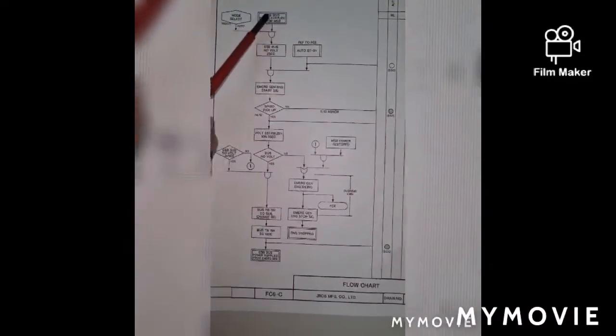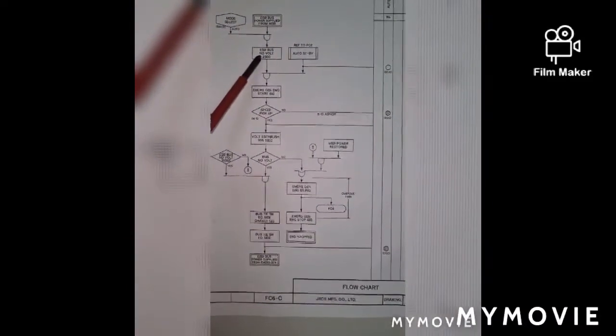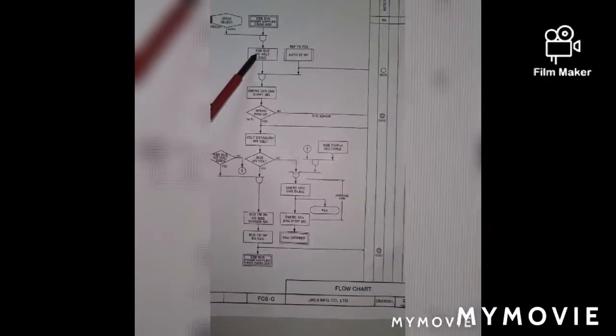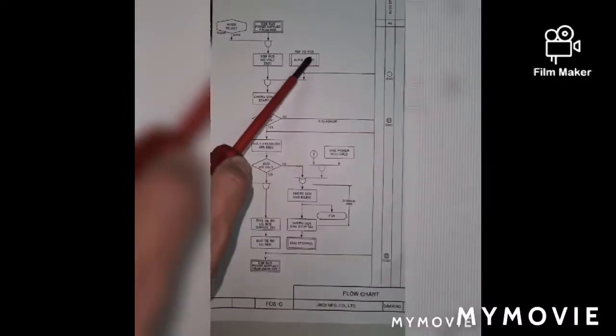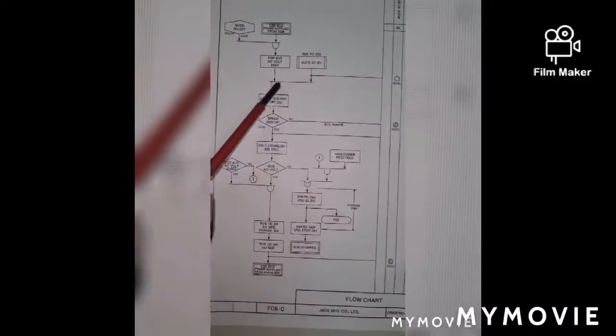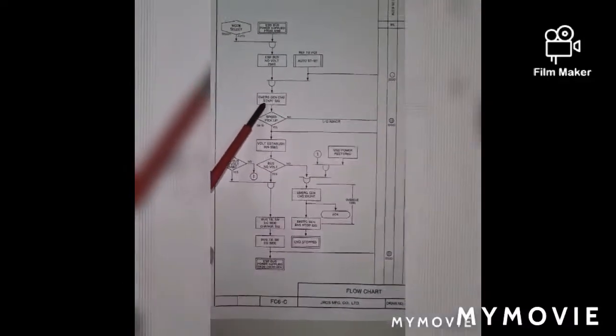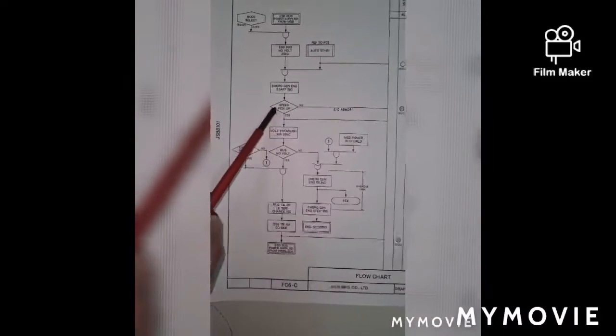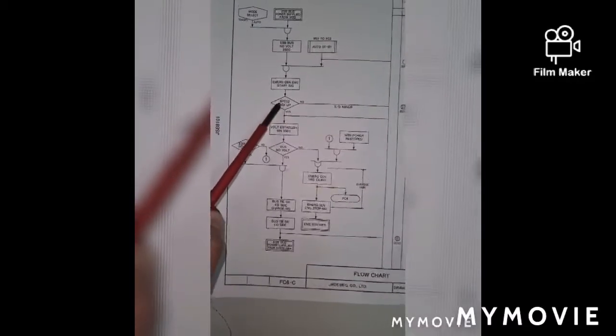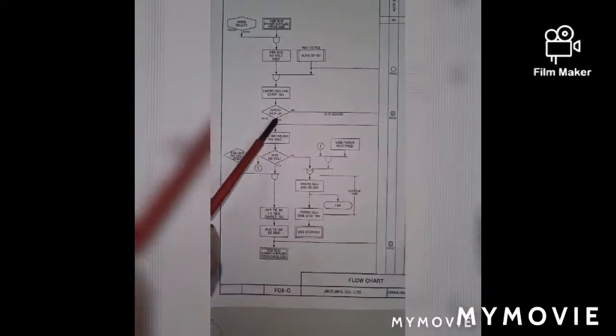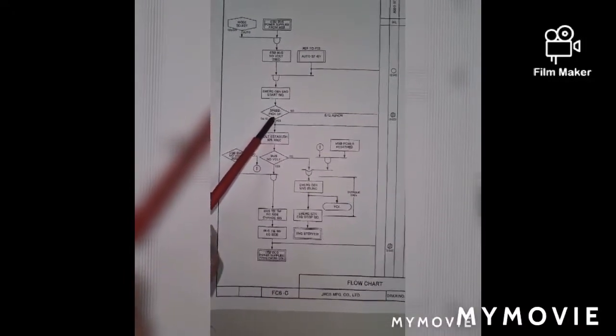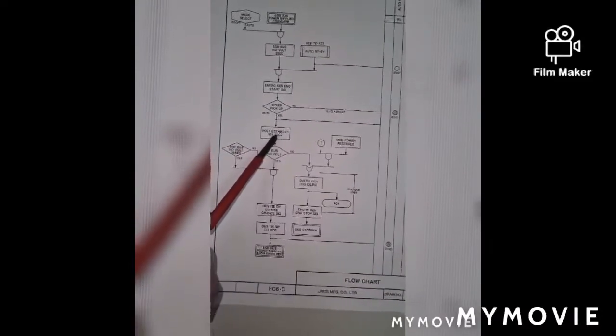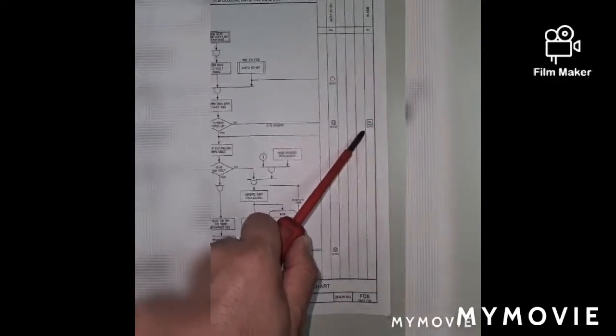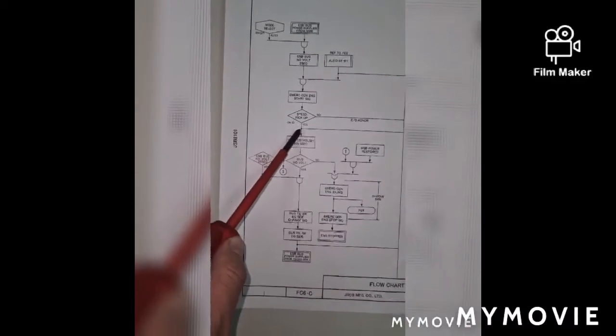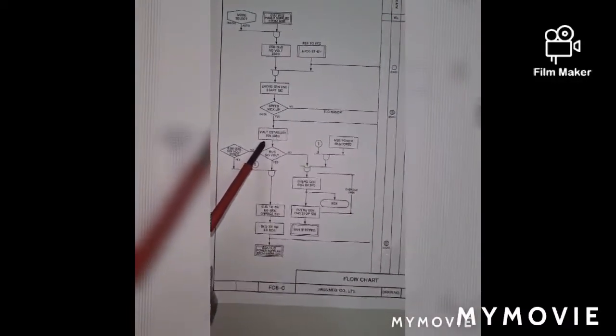Once the power blackout happens, within 2 seconds the emergency control panel detects that there is no voltage on the main switchboard, and the automatic start gives a signal to start the emergency generator. From here, there is a process judgment. On the judgment, the RPM pickup senses the RPM of the emergency generator, having 1800 RPM. If yes, it will go to the next process. If no, it will return and give an alarm: emergency generator abnormal.